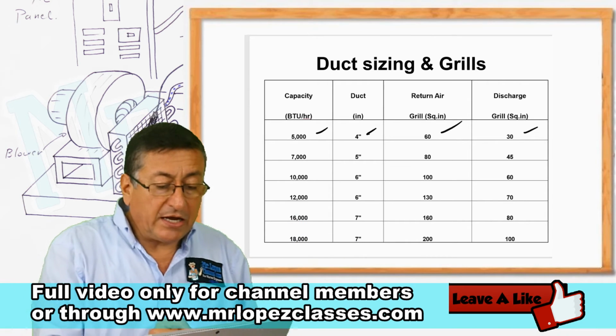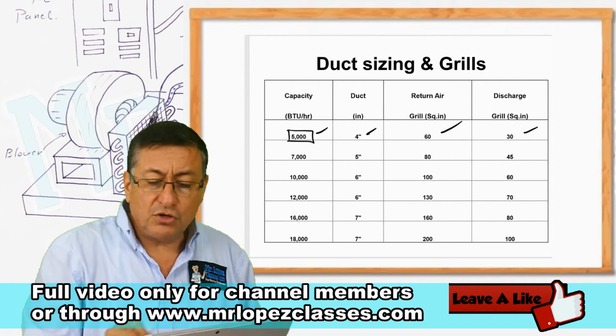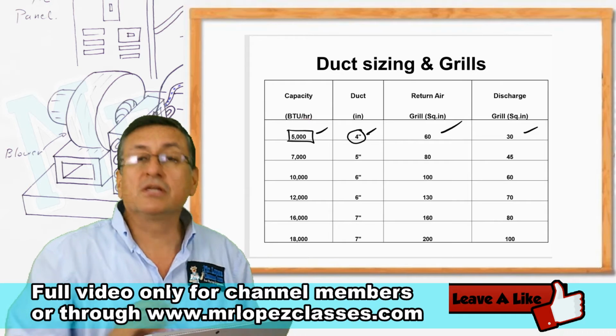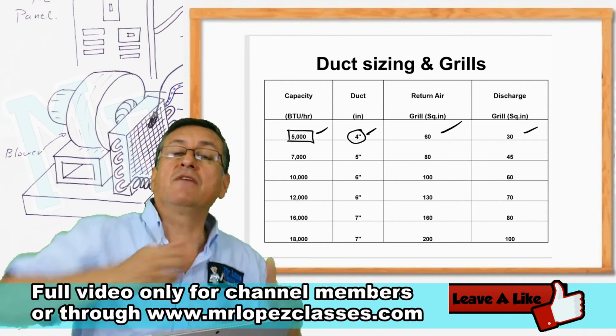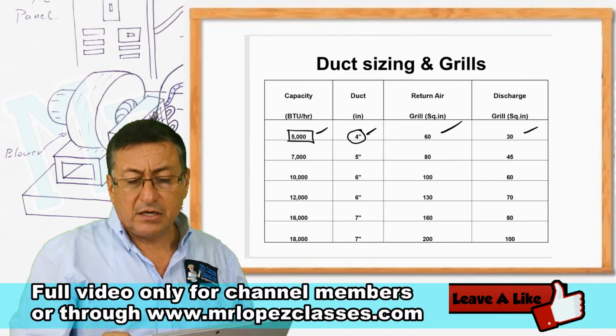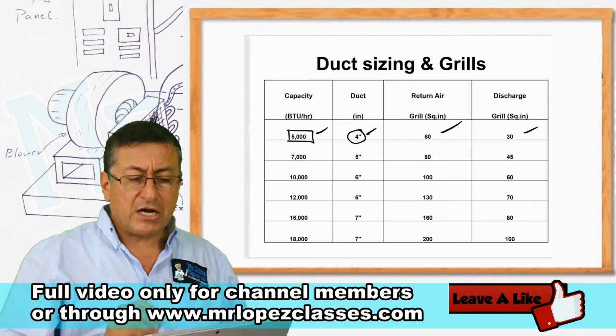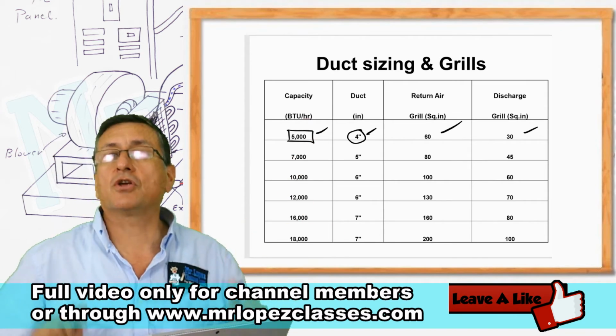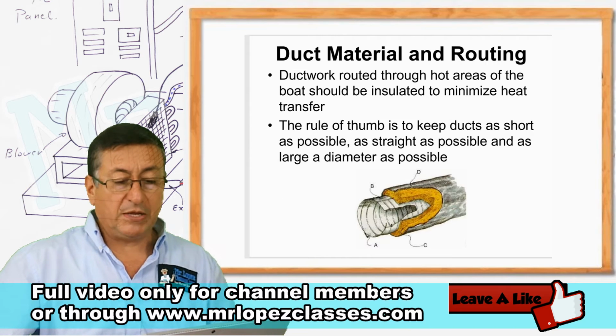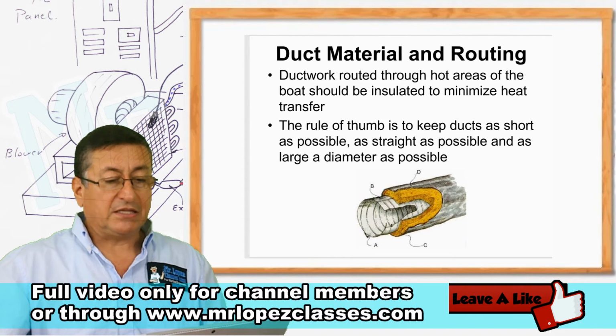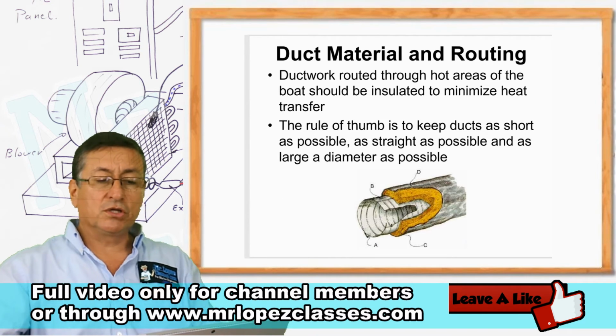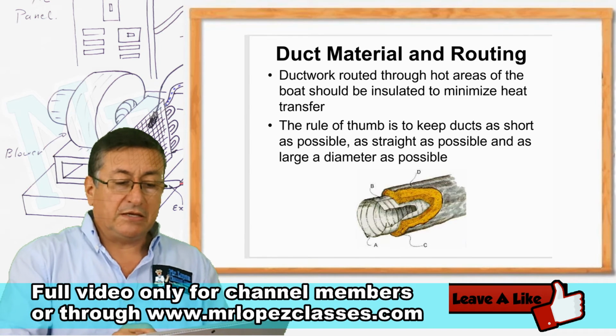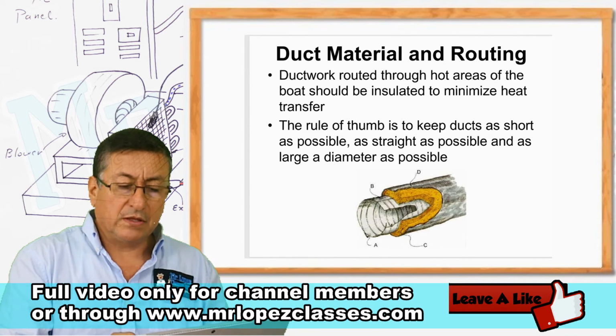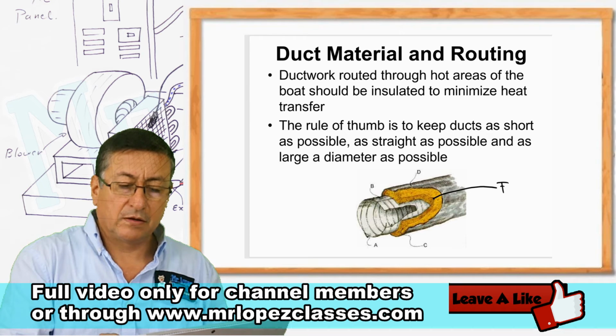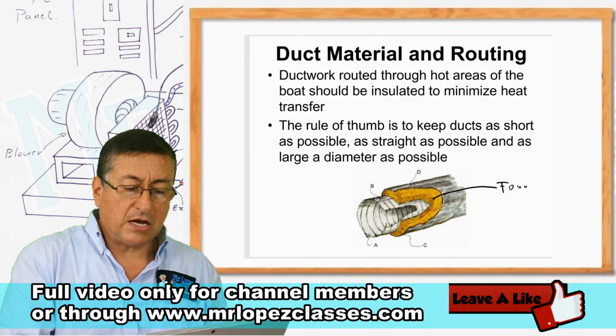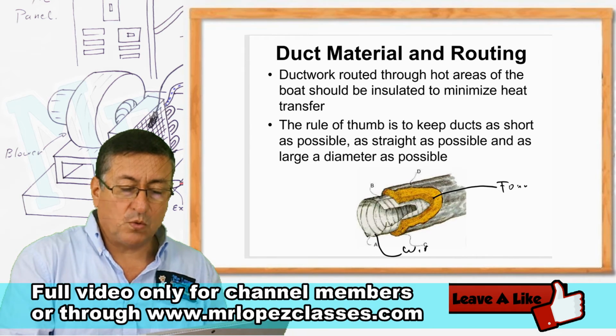In this particular case, for 5,000 BTUs, you need the diameter of the duct at 4 inches, and the grills 30 square inches the discharge and 60 square inches the return. Yes, my friend, this is not complicated. Look at the material. The material for the duct is basically foam. The yellow one is foam, and this is a plastic wire reinforced.